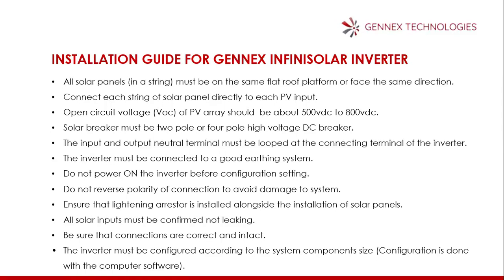The input and output neutral terminal must be looped at the connecting terminal of the inverter, which means all neutrals must be connected to a common bar, to a point. All of them are common. The inverter must be connected to a good earthing system.